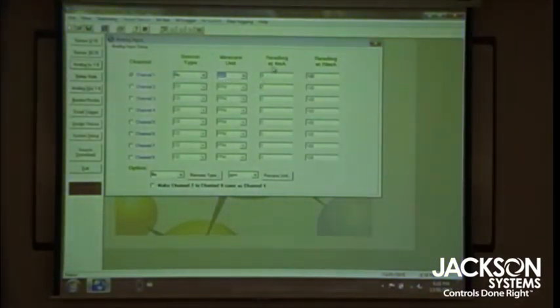Gallons per minute, and then you can go from zero to whatever you want. Maybe it's 1,000, I don't know. So you can also, if you have existing 4-20s, tie them into your controller, and it will come out on the display as that.